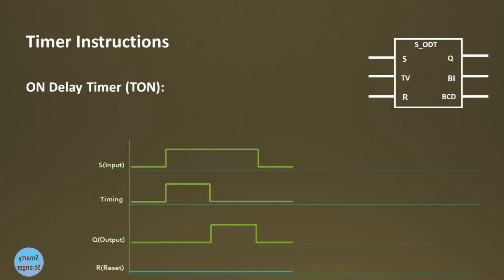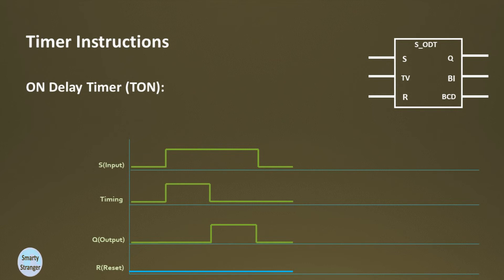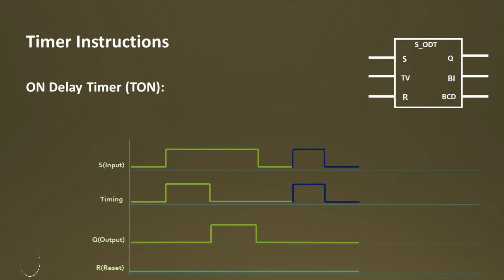Let's understand the On Delay timer via trends view. In the first cycle, if there is a positive edge at S input, the timer starts its timing, and when it completes its defined timing, output Q starts giving 1 or high. The output Q remains 1 as long as the input on S is high. In the second cycle, if S input changes from 1 to 0 before time elapsed, the timer stops immediately. In the third cycle, if the input on R changes from 0 to 1 while the timer is running, the timer stops.